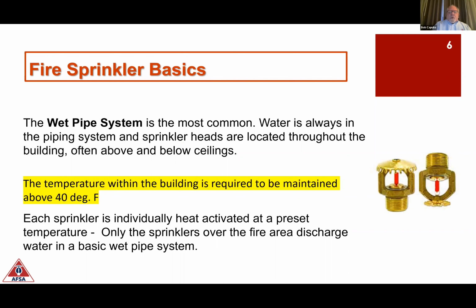There are 4 basic types of fire sprinkler systems, and you will most likely only be dealing with wet pipe systems, which are the most common. There's always water in the piping system, and the sprinkler heads are distributed throughout the building in a pattern on the branch line piping. So water's in the pipe. And so the only rule here is that the temperature within the building has to be maintained at or above 40 degrees Fahrenheit or 4 degrees Celsius.